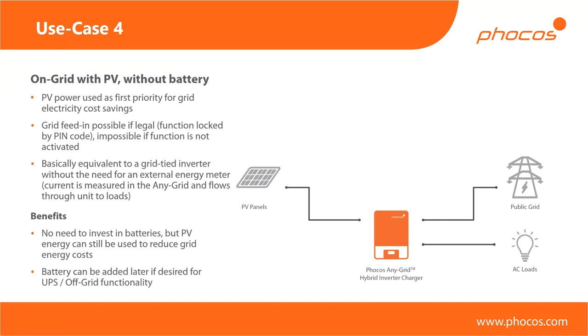We can still feed in if it's possible or legal in the region, and it's impossible if it's not activated. This is basically equivalent to a grid-connected inverter, except that if you're not allowed to inject, you would normally need an energy meter and communication between your inverter and that meter to ensure you're never backfeeding. You can avoid all of that by just connecting your loads to the Any-Grid, because it will handle all that for you.